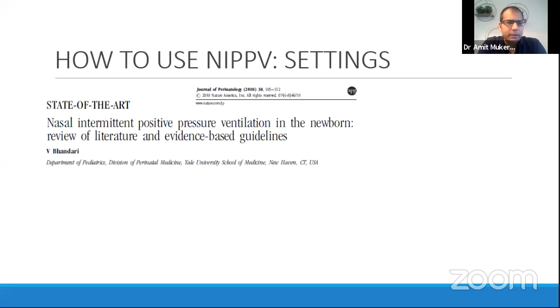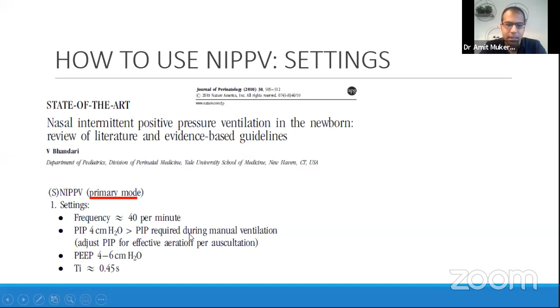Now, despite the limitations on NIPPV, Vineet Bhandari, from a number of years ago, actually published suggested settings for use of NIPPV. When used as a primary mode, so you're starting a baby post-transition, post-resuscitation, these are the suggested settings: frequency of 40, PIP 4 centimeters above whatever the PIP was required during handbagging, let's say, and a PEEP of 4 to 6 with an I time of 0.45. When used as a post-extubation mode, the suggested frequency was between 15 and 25, PIP 2 to 4 higher than whatever was on conventional settings, then adjust the PIP for effective aeration based on auscultation, and a PEEP of 5 or less.